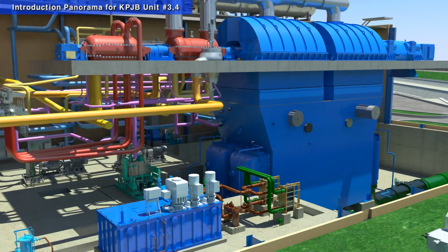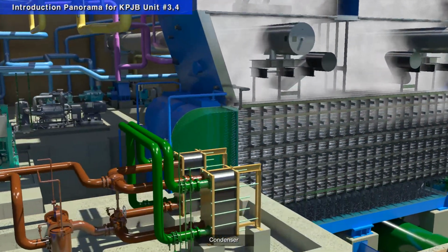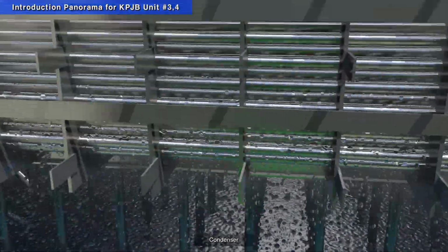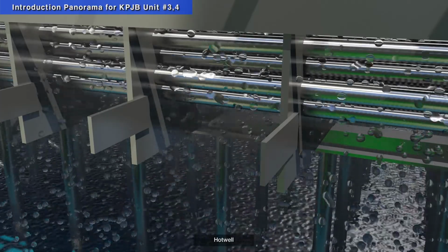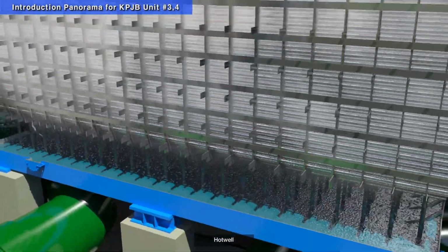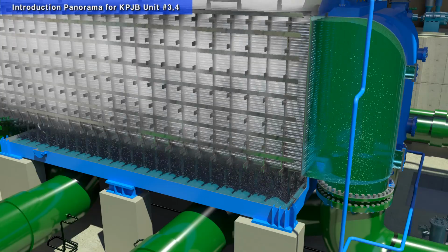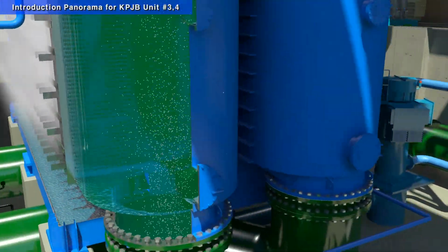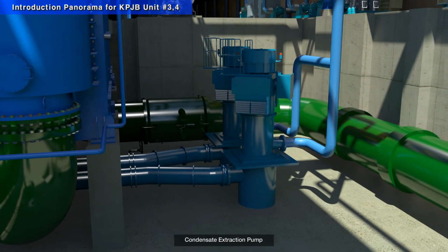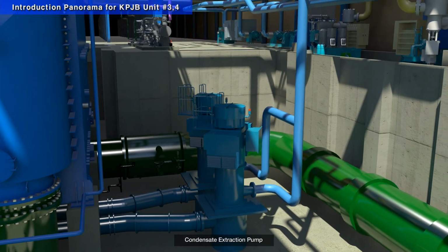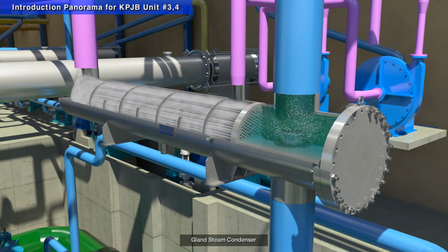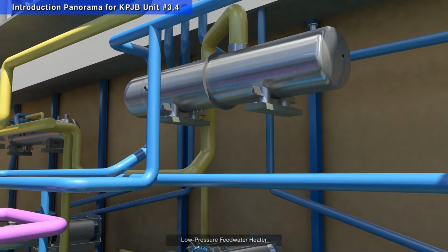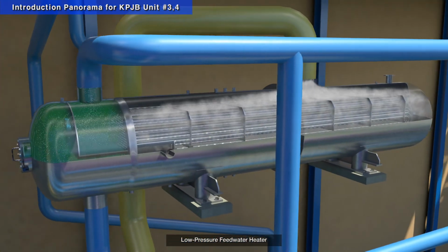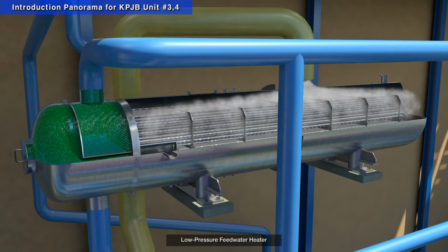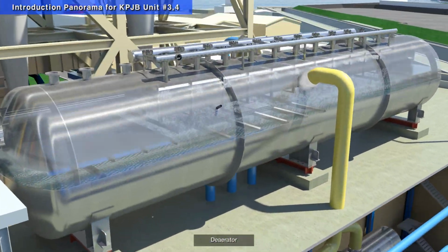The condenser consists of one shell per unit and gathers the low-pressure turbine exhaust and various types of drain to the hot well after condensing through heat exchange by cold seawater. The condensed water, which is gathered at the hot well, goes through the gland steam condenser and low-pressure feed water heater by condensate extraction pump. Then it becomes feed water, from which air and other dissolved oxygen have been removed after going into the deaerator. This feed water goes to the boiler economizer after going through the BFP and high-pressure feed water heater.